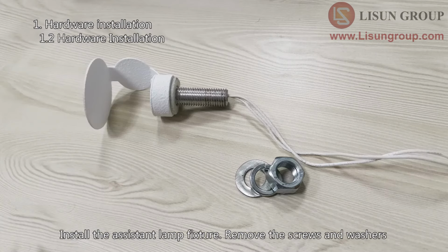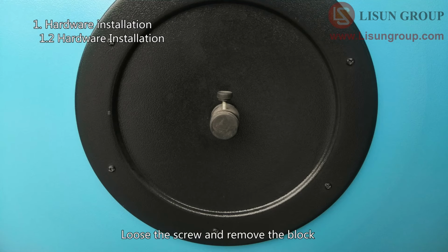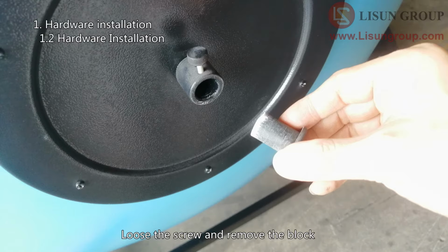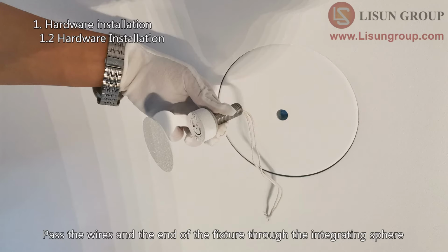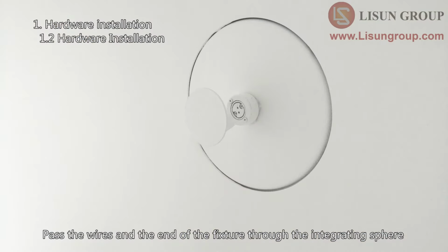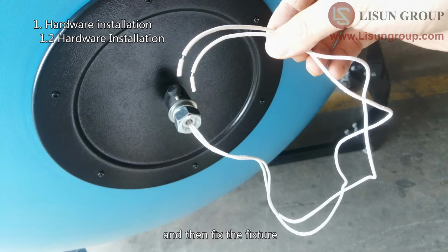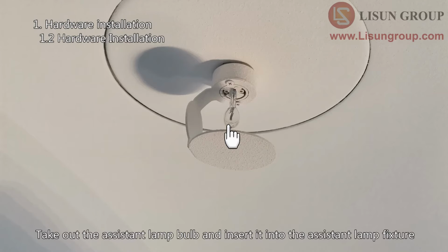Install the assistant lamp fixture. Remove the screws and washers. Loosen the screw and remove the block. Pass the wires and the end of the fixture through the integrating sphere, and then fix the fixture. Take out the assistant lamp bulb and insert it into the assistant lamp fixture.